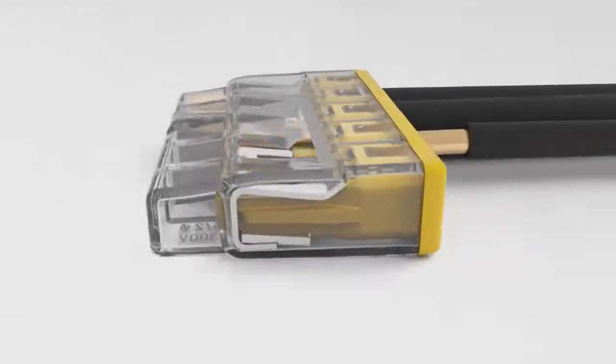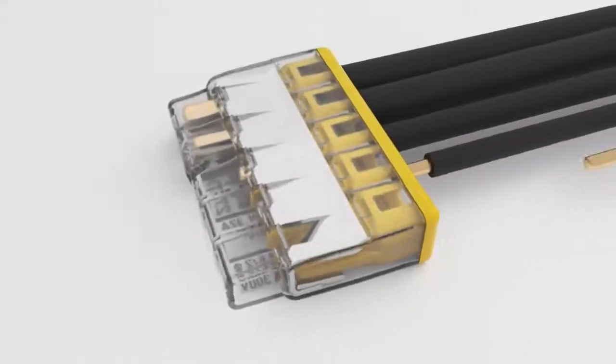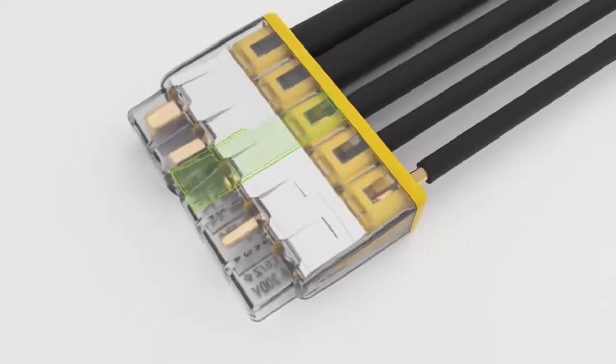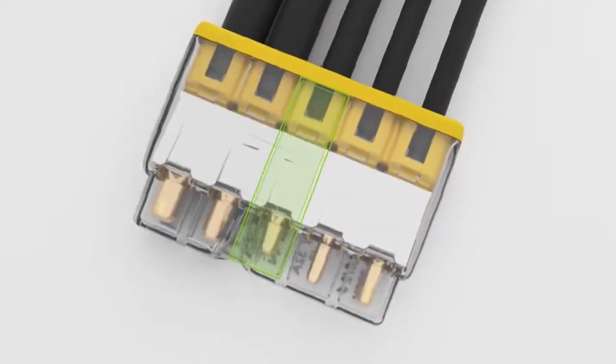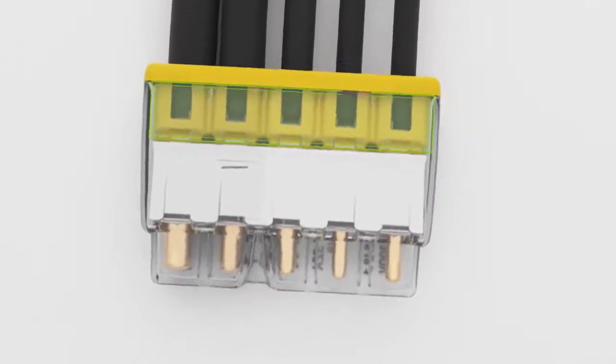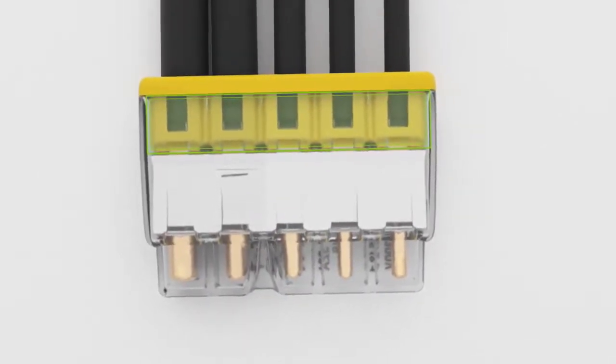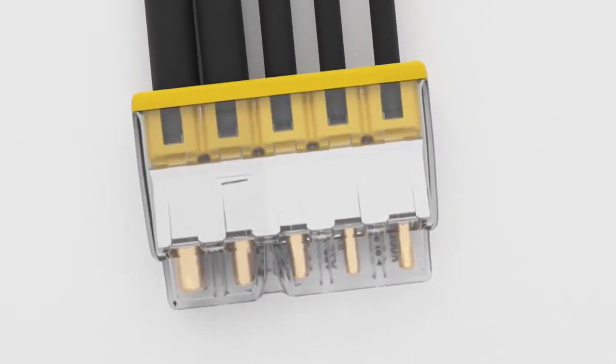The transparent housing permits visual inspection of the conductor position. If conductors are not inserted far enough they're easily identified. The viewing port in the housing on the non-labeled side allows incorrectly stripped conductors to be easily recognized.